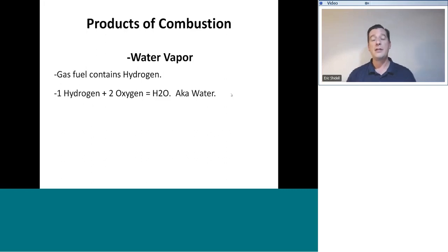Very important to realize that water vapor is present in gas combustion. And if you see evidence of water vapor or liquid water in a flue in a place where it shouldn't be, you have an issue. And that's something to go after. So very important to realize water vapor is a normal and natural byproduct of natural gas combustion. In fact, almost any combustion is going to have water vapor as a byproduct.